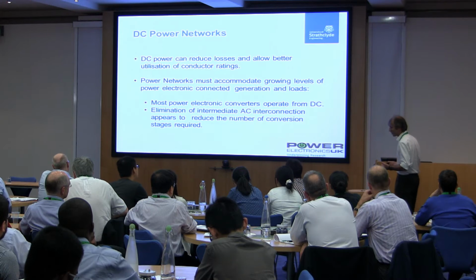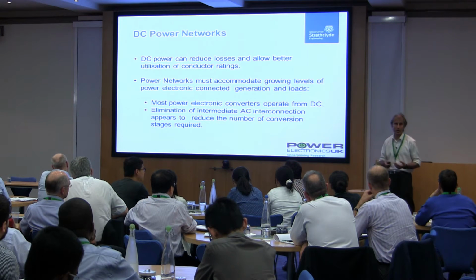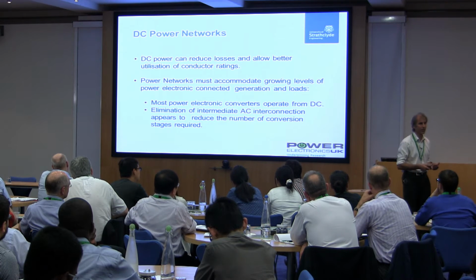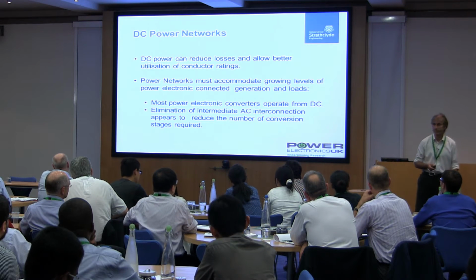It also probably starts to become justified in power distribution or power collection systems such as offshore wind energy, where the area of the cable network is starting to reach hundreds of kilometers. It's not got exactly the same issues as long-distance transmission, but there's still a lot of reactive power that has to be put into that cable network to keep them energized.